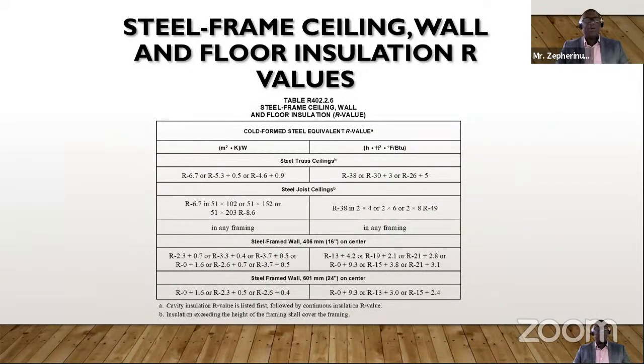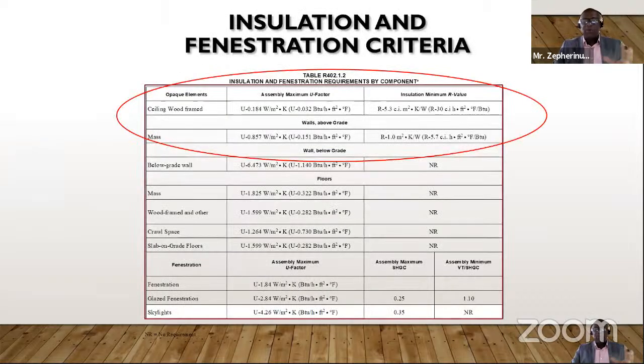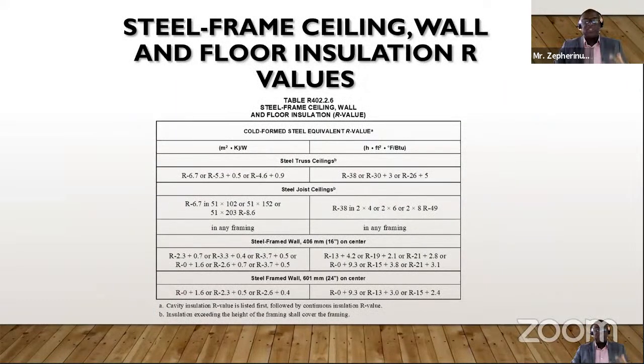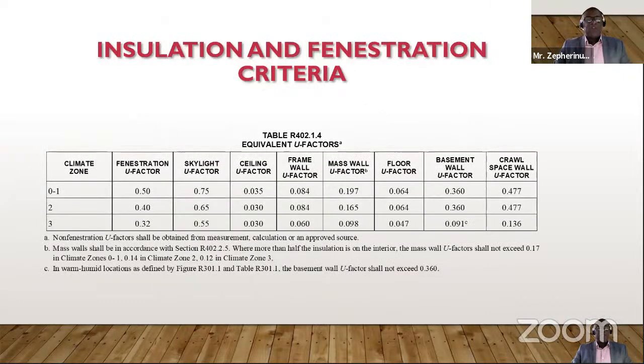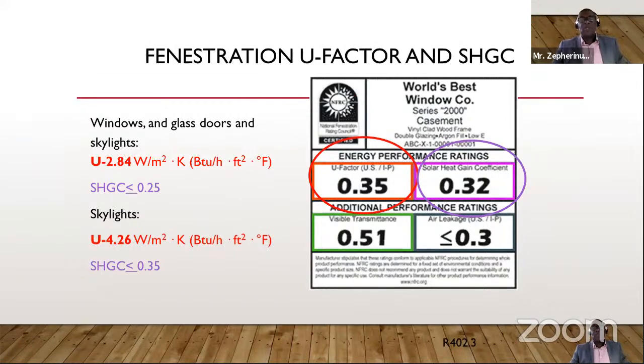So as we continue, again, if you have a steel frame ceiling, wall, and floor, the recommended insulation R values for steel frame, and this would be for wooden and concrete buildings, for steel frame buildings, residential buildings, the corresponding thermal resistance for your ceiling, walls, and the floors. Insulation and fenestration criteria, depending on your climate zone and the respective tables. So as you utilize the code, most of our Caribbean countries are within climate zone 0, meaning that there are over 6,000 cooling degree days at 10 degrees C. And so the climate zone 0 would help you to determine the fenestration requirements as per the table listed here. What are the U factors depending on your climate zone? Fenestration U factor and the solar heat gain coefficient.